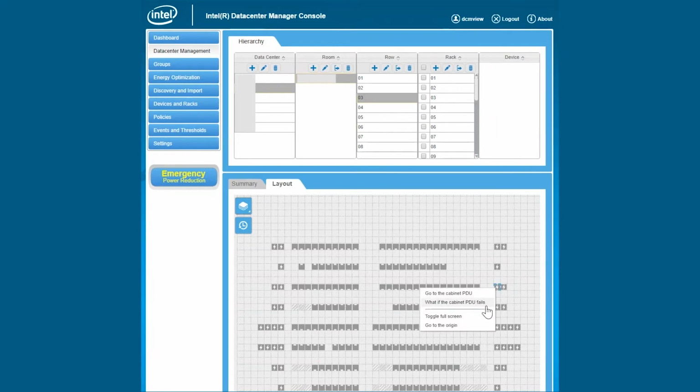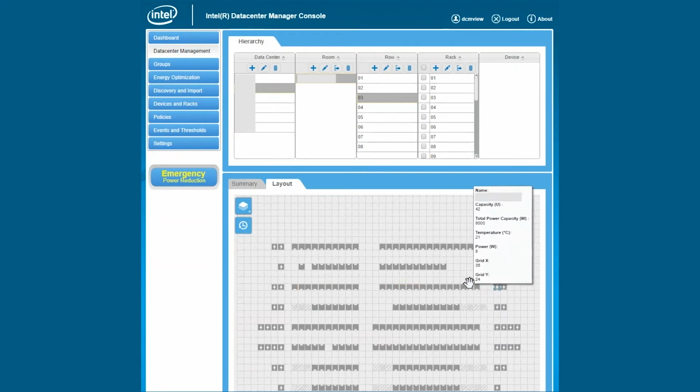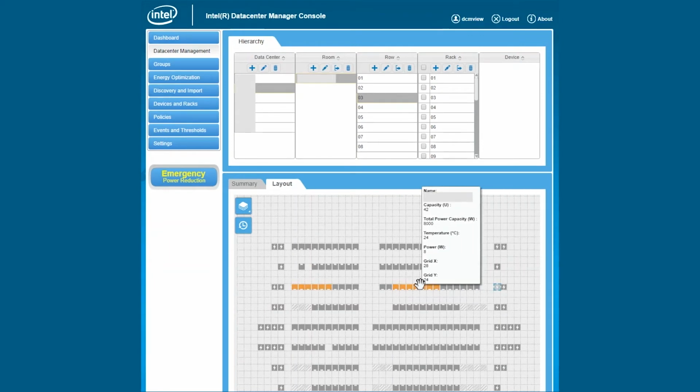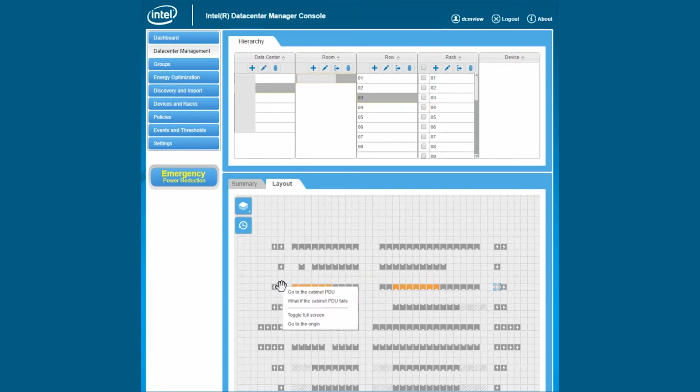And then if I go to the layout, I can actually create a simulation and see what happens if this electrical panel fails. So let's click this, and this is only a simulation. Immediately you can see that if this row power distribution unit is failing, these are the racks that will lose one of their power feeds. And if I find its twin, let's simulate this. So if I lose these two, all the racks that are colored now or blinking between gray and red will actually lose their power. And this actually reflects the redundancies that we have in this specific data center. And now let's remove the simulation.